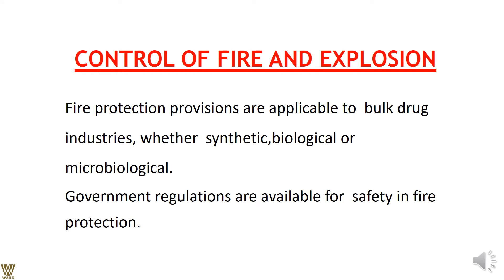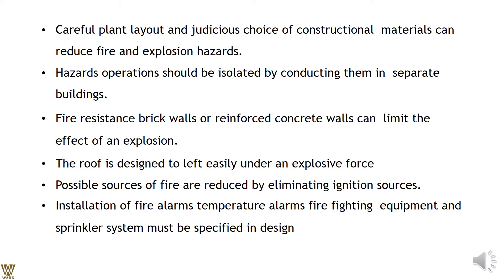Fire and explosion control provisions apply not only to large pharmaceutical industries but also where synthetic, biological, or microbiological materials are present. Government regulations regarding fire safety and protection must be understood. Careful plant layout and judicious choice of construction materials can reduce fire and explosion hazards. Hazardous operations should be isolated in a separate building to limit the spread of fire or any major catastrophe.